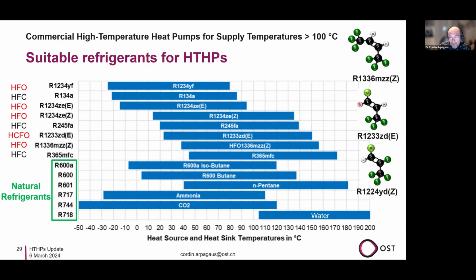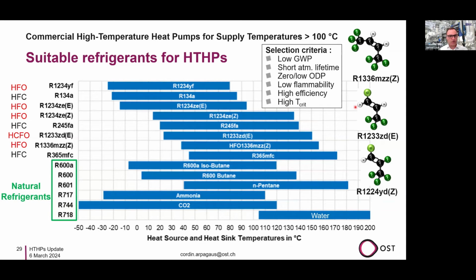Some also have a chlorine atom, here the R1233zd(E), and that could be a problem because the ODP, the ozone depletion potential, is not zero - it's 0.0034, so almost zero. But in some countries this is prohibited, though some have exceptions. So the selection - just because we're running a touch behind schedule, should we jump over a bit or speed up a bit on this refrigeration one?